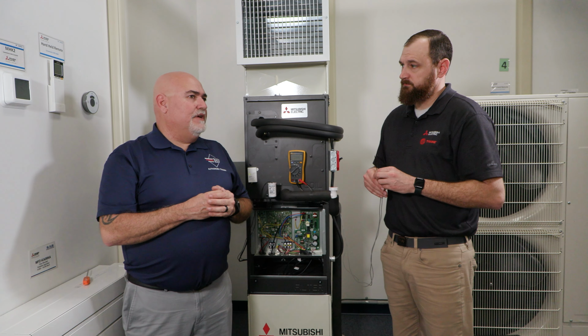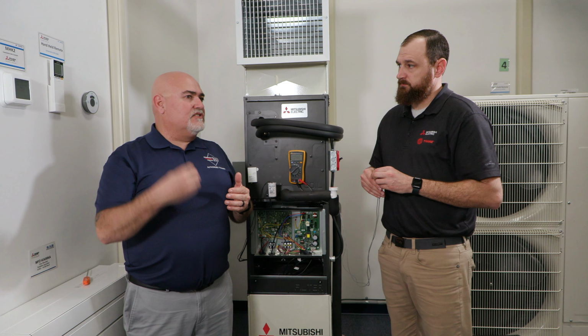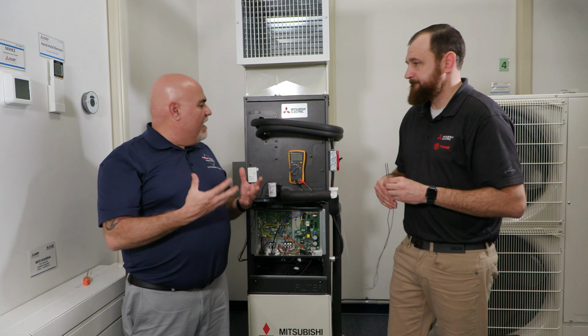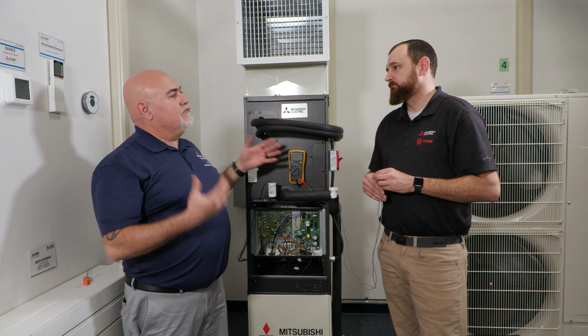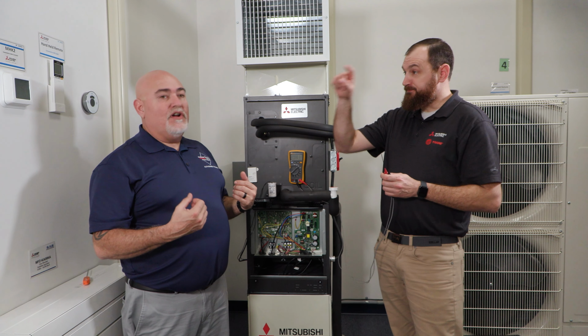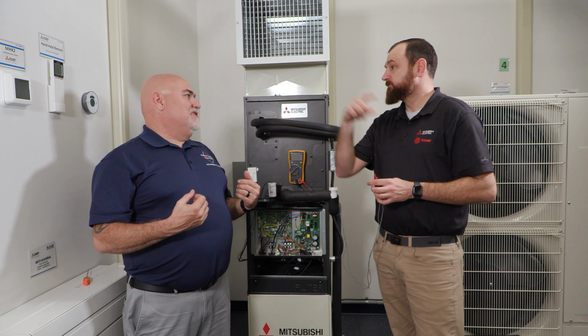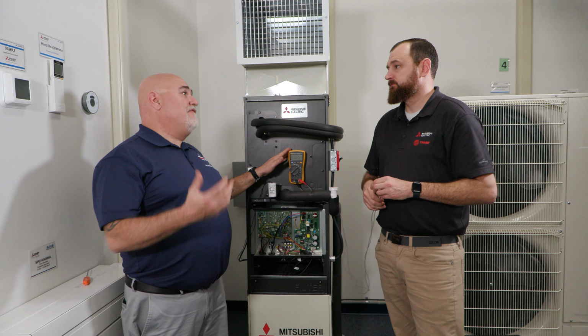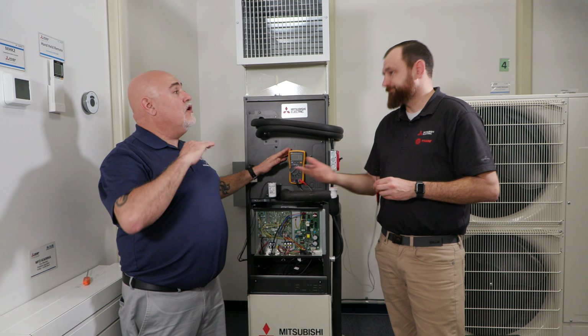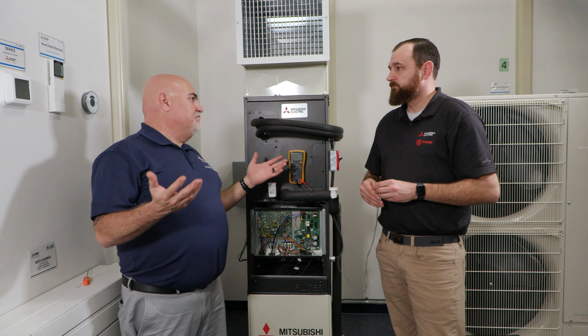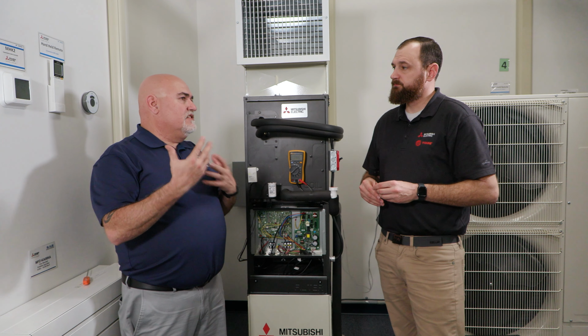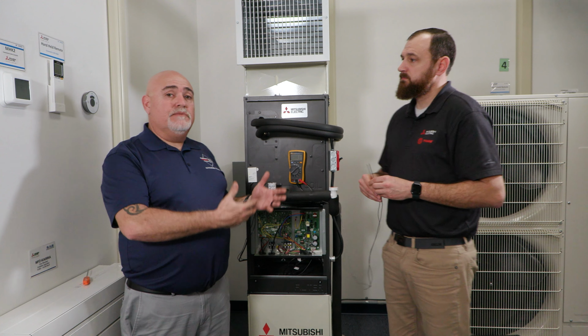Here's the trick though: because this happens so fast as the motor is spinning, we don't have a multimeter fast enough to read that rotational feedback when it's running. If it's running, what you're normally going to see is half of 15 volts, which is 7.5 volts constant. That doesn't tell us if the motor is defective, or if we're getting a pulsing voltage. So this is the reason we're doing it with the system off.